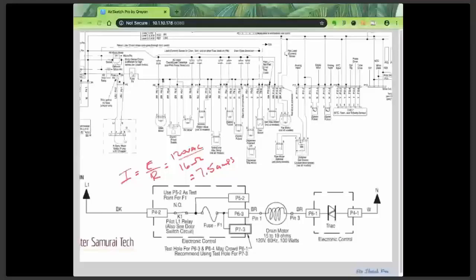The problem is that I can't calculate motor amps from winding resistance, because motors are inductive devices with large inductive reactance plus their normal resistance. Your meter only measures normal resistance. It does not measure inductive reactance. Inductive reactance is an opposition to electrons that is developed in a motor winding when there's actual alternating current voltage applied. So you're not going to see that normally with your meter.